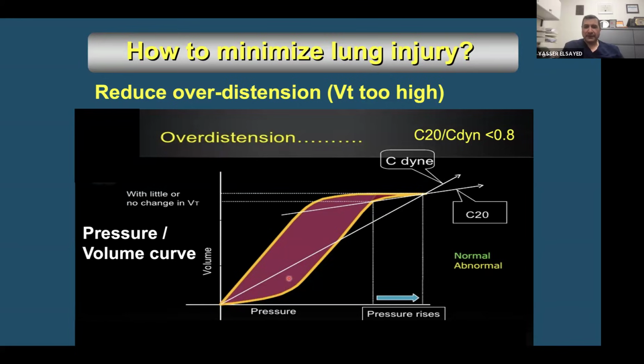Next, one of the most important interventions: you apply an axis on the main curve from the beginning to the end, and another axis on the top part, the last 20%. You have an angle in between, and this angle is calculated by the machine. When both lines are identical, it means you don't have an angle, you are very good, and the compliance at the last 20% of the cycle is exactly the same as the entire cycle. But if the line is flatter for the last 20%, because the infant is struggling more with compliance, it means that you have over distension.